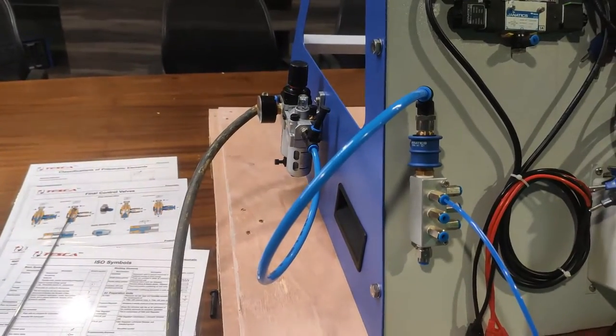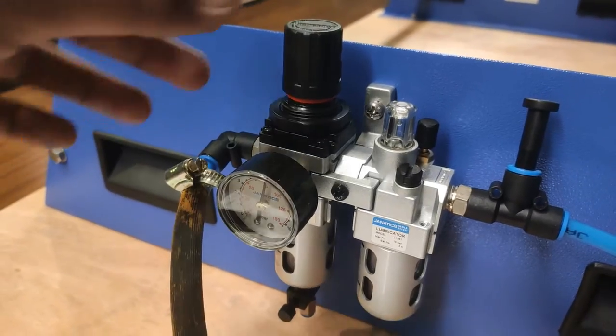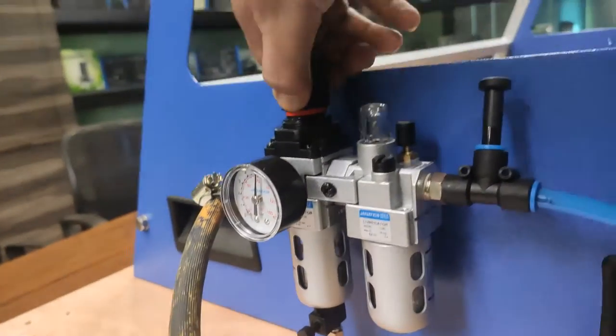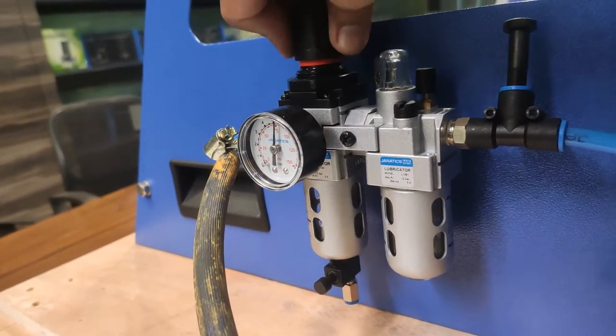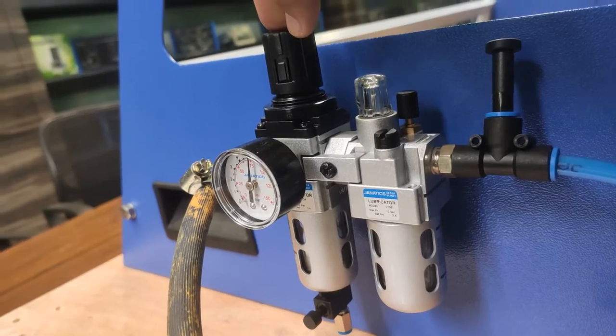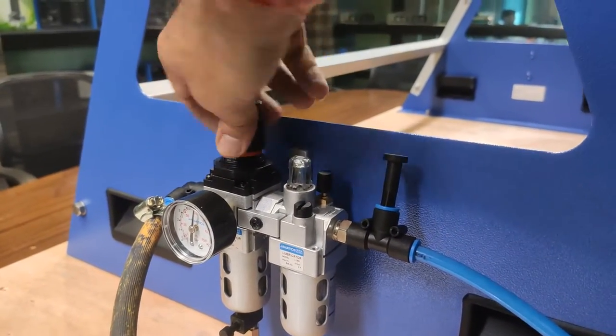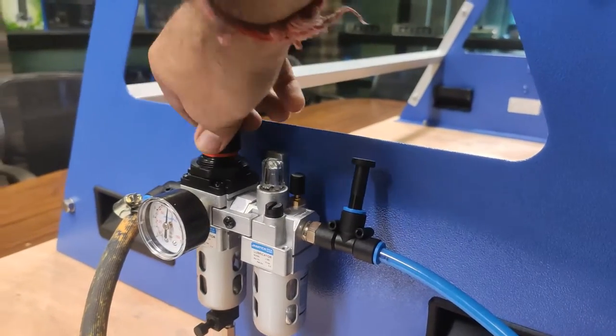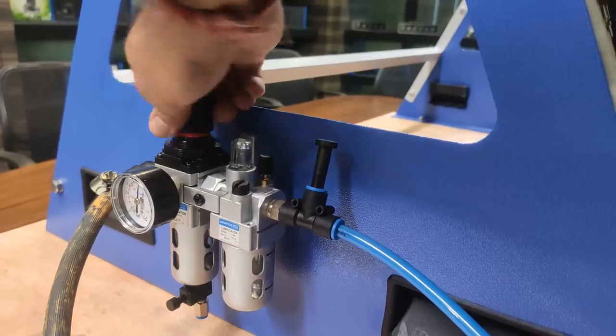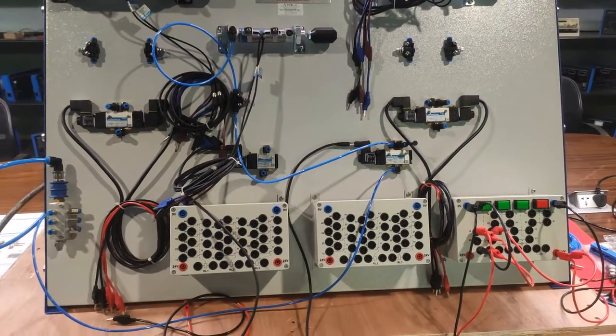The pressure gauge shows 75 PSI. You can control pressure using the pressure regulator. Moving the regulator knob increases or decreases pressure. The regulator also has a lock system: press the knob downward to lock it, and pull it upward to enable rotation. Turning the knob clockwise increases pressure; turning it counter-clockwise decreases pressure.